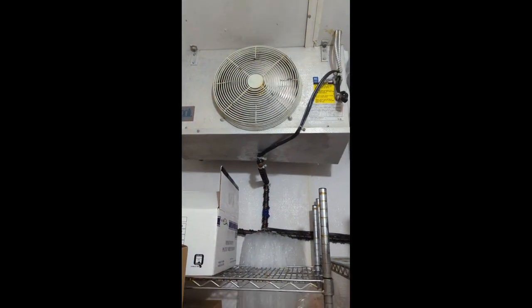We also looked at a leaking drain at a fish and chip place — this time in a freezer. The evaporator had this huge waterfall of ice coming down. They told us the typical story: 'Oh, we didn't realize this until yesterday morning.' But that ice waterfall had been building up for some time. And they had tried to repair the burst pipe with tape. I know tape fixes everything, but in this situation, it did not.